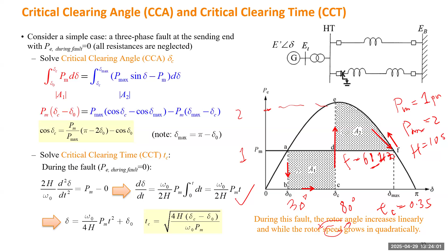Let's talk about the more general case. Here we assume the electric power during the fault is positive, not zero. We are going to consider 3 different P's. The largest one is the pre-fault P, the next one is the post-fault P, and the smallest one is the during-fault P. When we calculate the accelerating area, we need to calculate A1, which is the area above the during-fault P but under the mechanical power. For the decelerating area, we need to calculate A2. A2 is the area above the mechanical power but under the post-fault electric power.